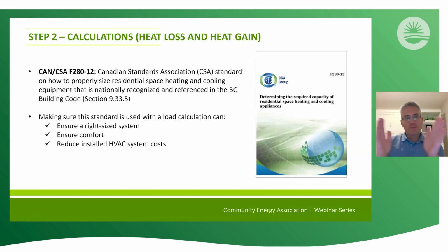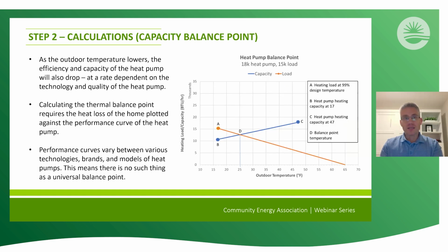good. Calculations. Calculations start with load calculations, and there is a CSA standard which really governs proper sizing of residential heating and cooling systems. It's recognized in the BC Building Code as a requirement for new construction, and basically it's the methodology for determining the heat loss and heat gain for the home. And so contractors need to know that standard, and they need to be using tools that are verified to meet that standard to do their load calculation to ensure the system is right sized and is going to provide the comfort. Right sizing means appropriate cost too. In terms of the HVAC system, it's not going to be oversized, and thus homeowners aren't paying for a larger system when they didn't necessarily need it. So it starts with the heat loss and heat gain.